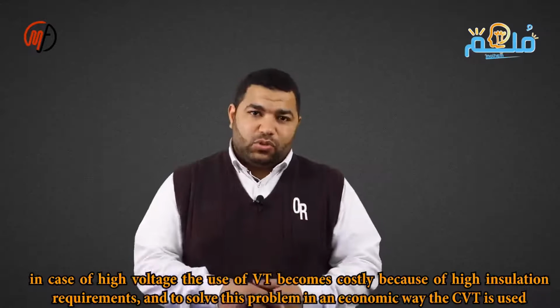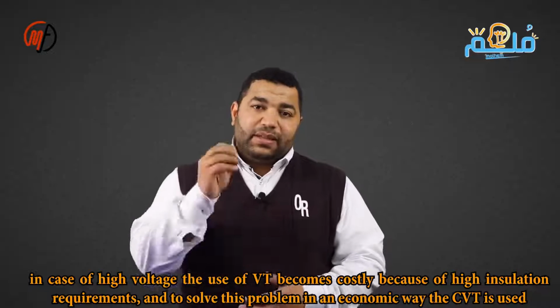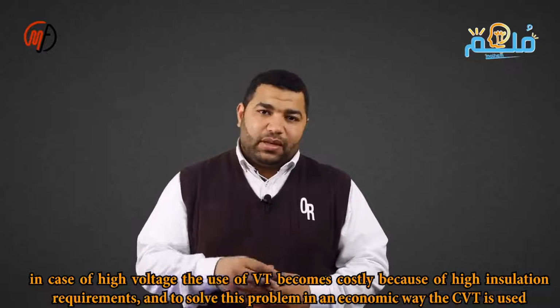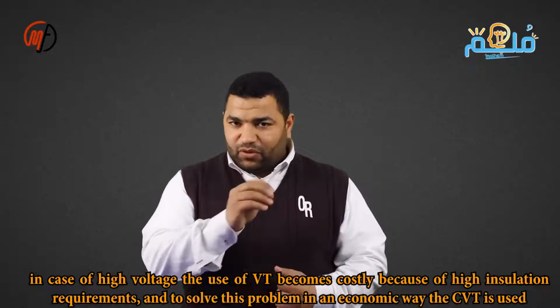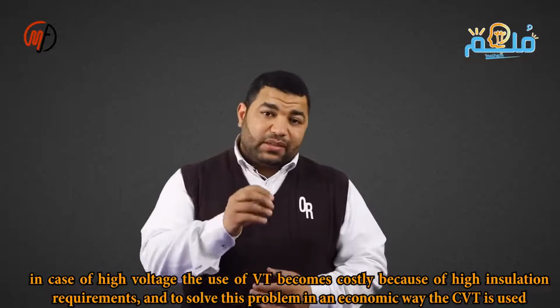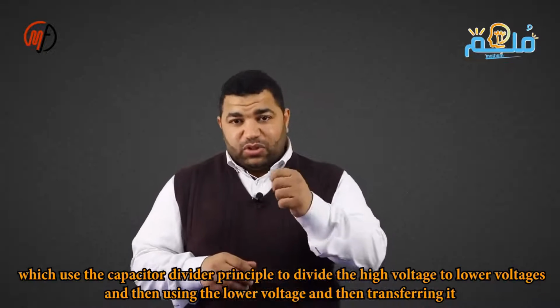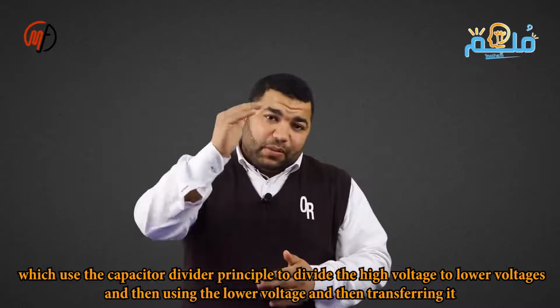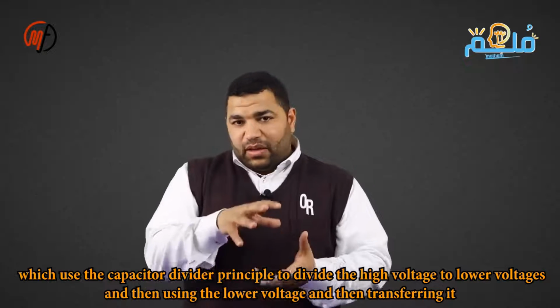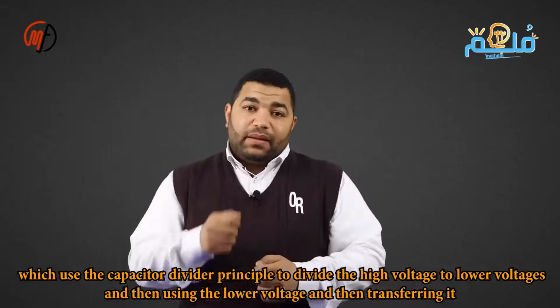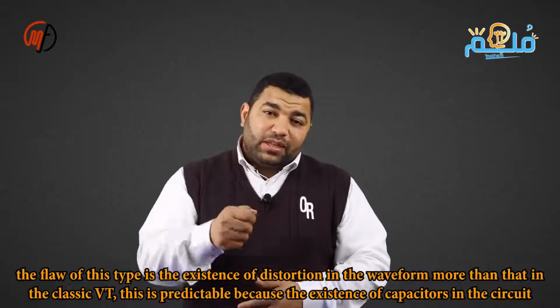In high voltage situations, using a VT is costly. A CVT steps down high voltages cost effectively. A drawback of the CVT is more waveform distortion than a VT due to the capacitors, but modern digital relays can restore the original waveform. Capacitors in series drop the voltage for VT conversion. Low impedance requires high capacitance.